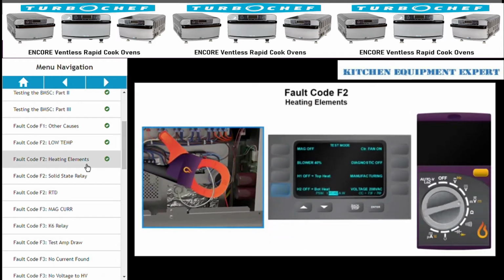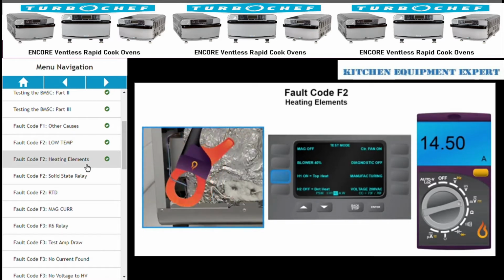Go to test mode, run H2. Do you have current on K4? If not, then inspect the bottom heating element. Then run H1. Do you have current on K5? If not, inspect the top heating element.